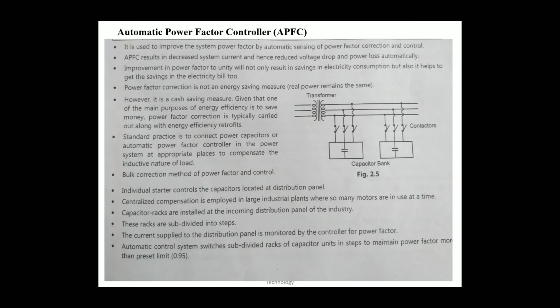The next, automatic power factor controller, that is the APFC panel. It is used to improve the system power factor by automatic sensing of power factor correction and control. APFC results in decreased system current and hence reduces voltage drop and power loss automatically. Improvement in power factor to unity will not only result in saving in electricity consumption, but also helps to get a saving in the electricity bill too. Power factor correction is not an energy saving measure, that is, the real power remains the same.